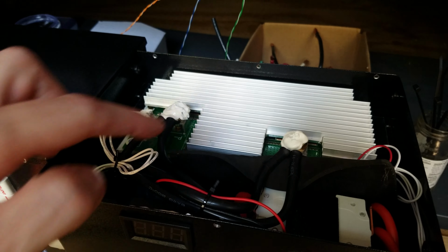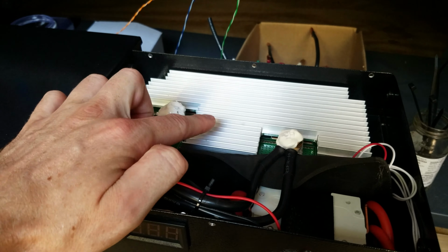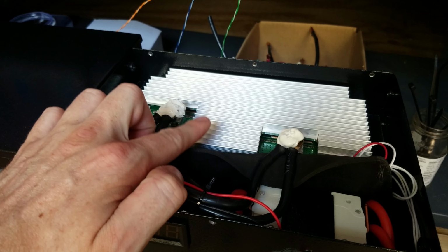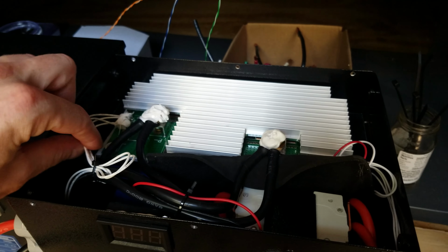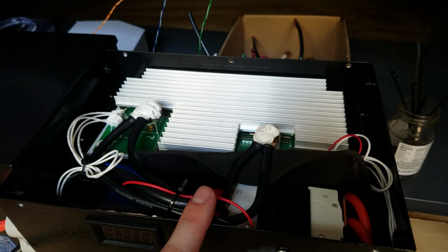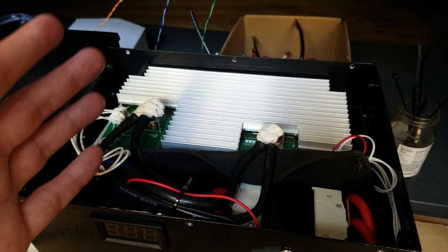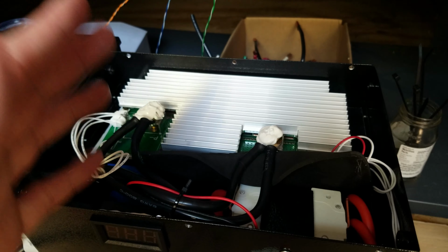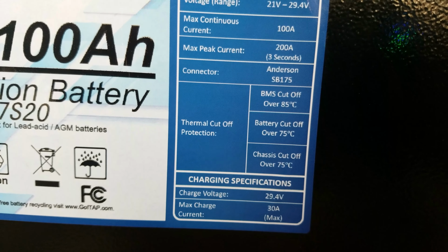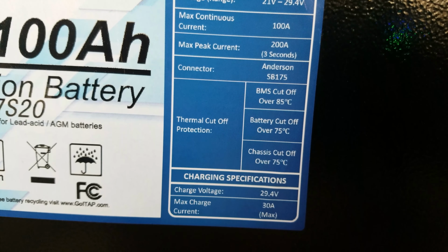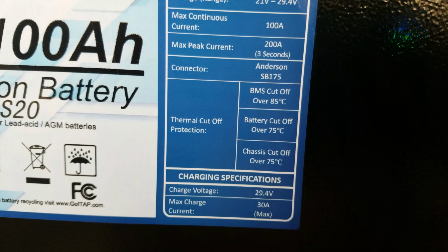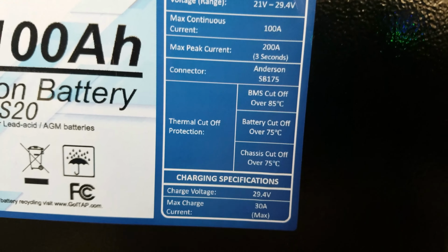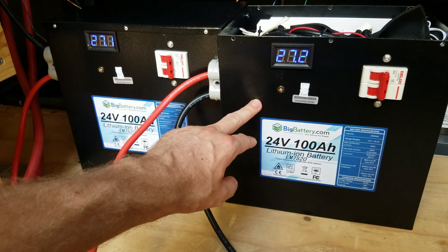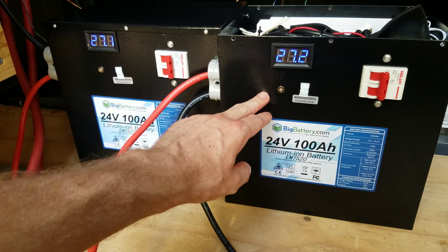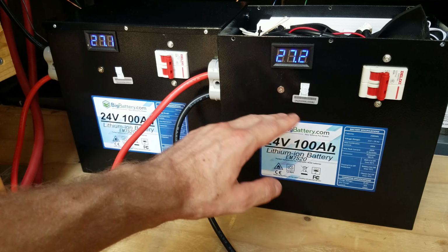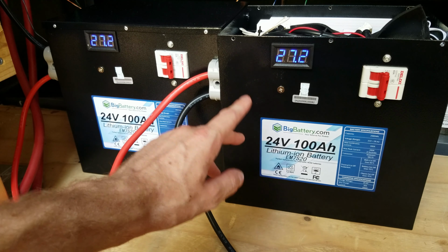However, I will say that it is very cool and very reassuring to see this BMS working exactly as it was designed with the safety measures in mind. So these temperature sensors picked up on the over temperature in this enclosure, and it shut it down with no problems at all. 100 amps, it just flicked it right off. That was pretty cool to see. So on the front label, the chassis cutoff is set at 75C. So I would say 150C is definitely greater than 75C. So with that in mind, I'm going to stop the clothes dryer discharge test, and I'm going to go turn on the air conditioner. We'll put a slightly lower load on it and see if it reacts any differently.